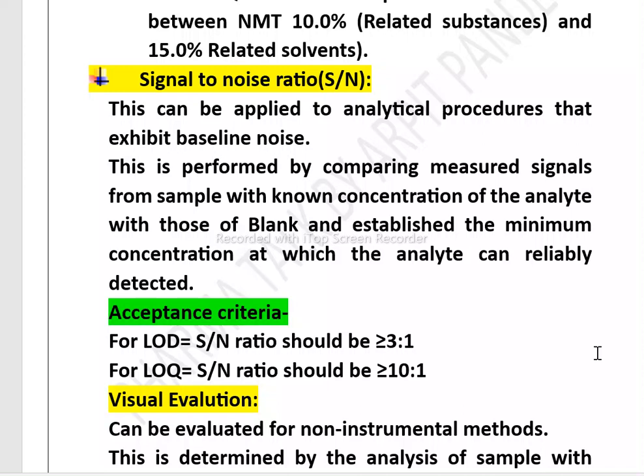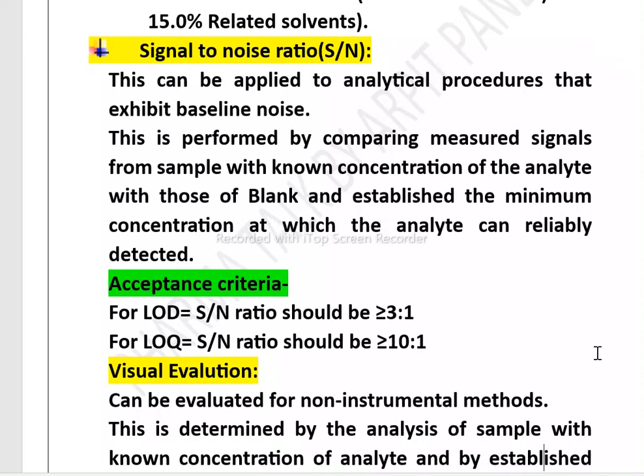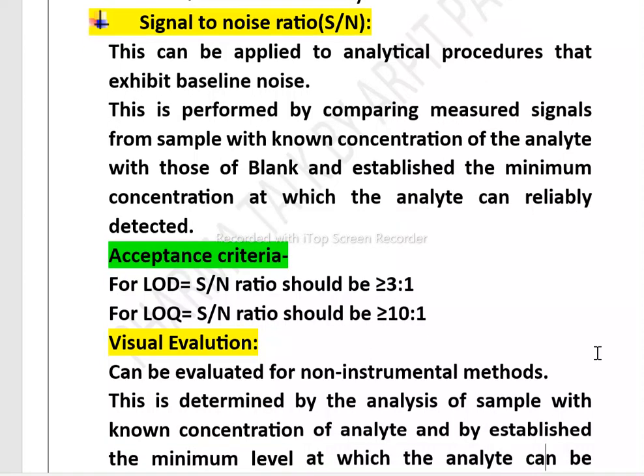For LOQ, the acceptance criteria is that the signal-to-noise ratio should be greater than or equal to 10:1.